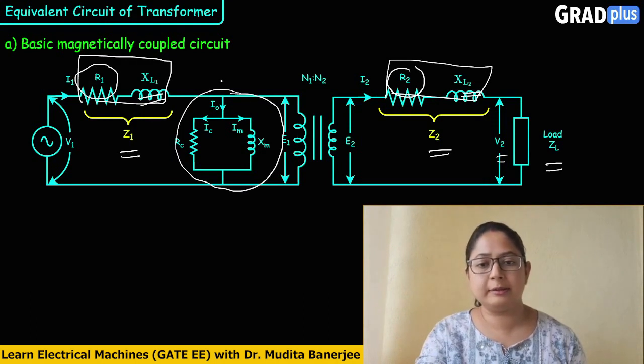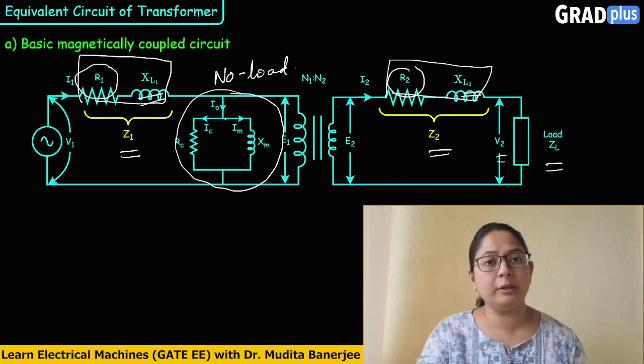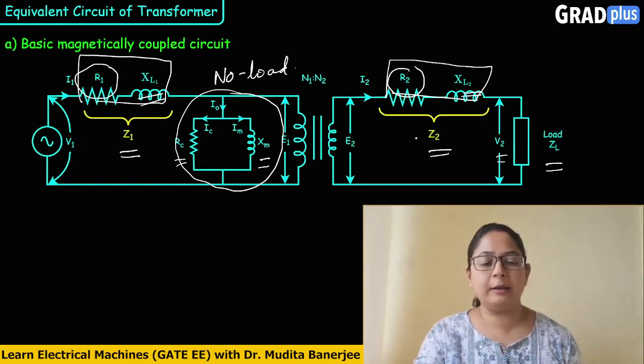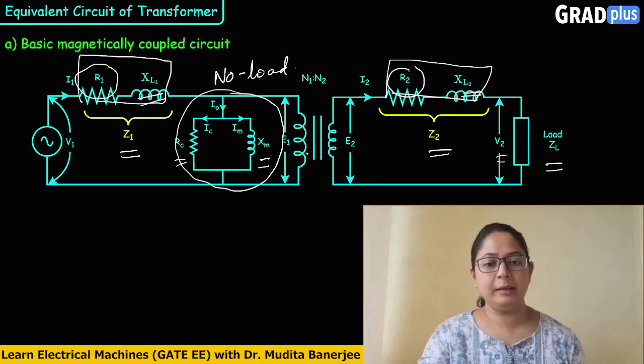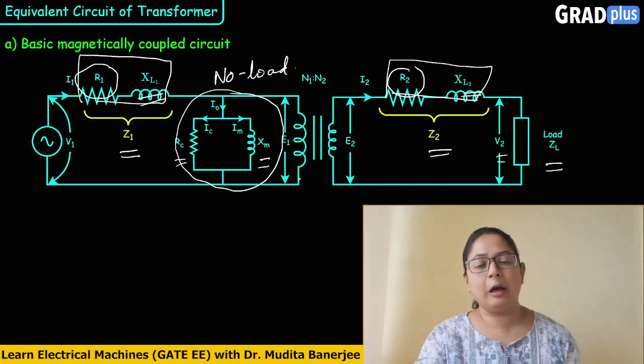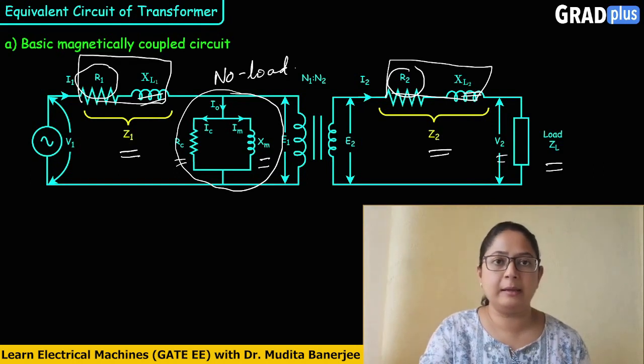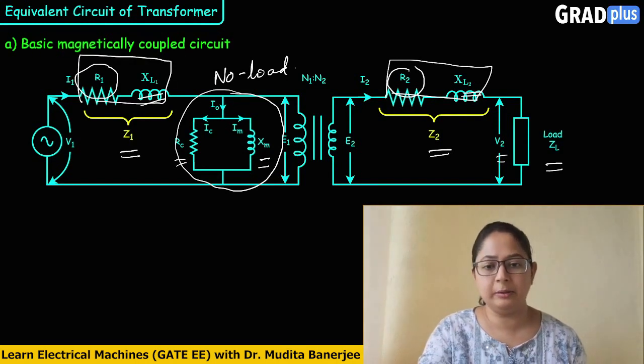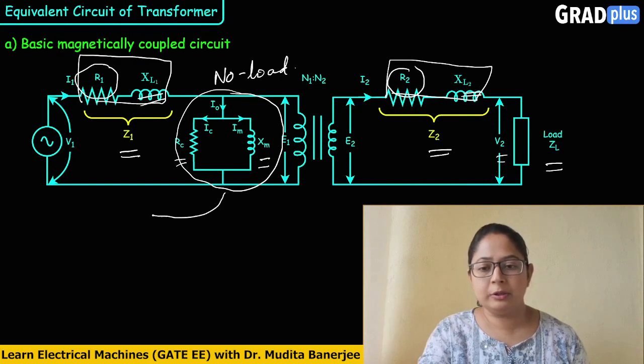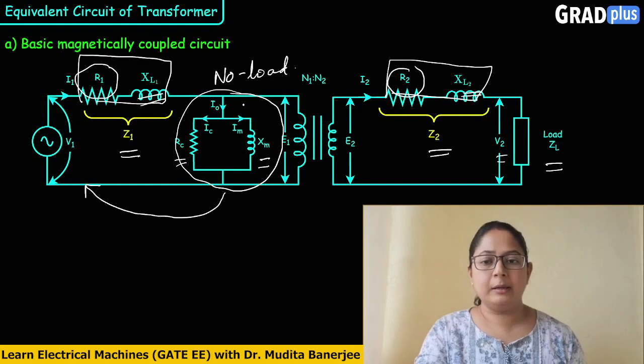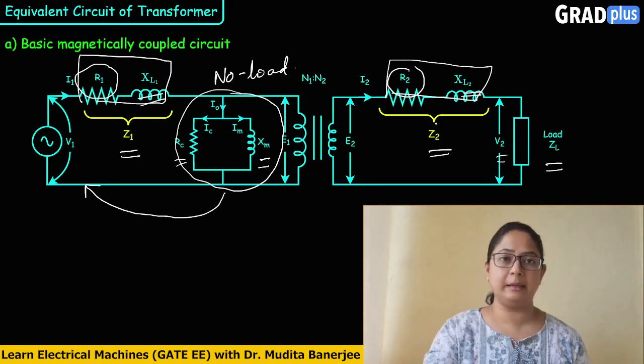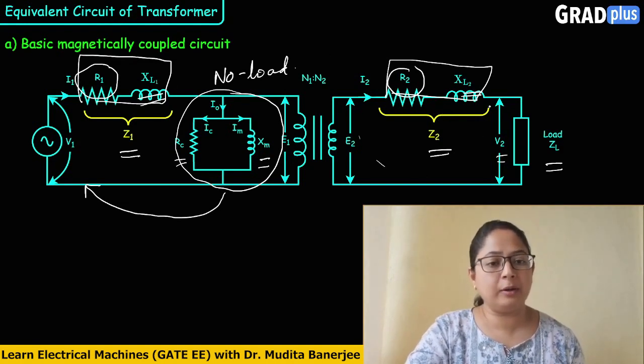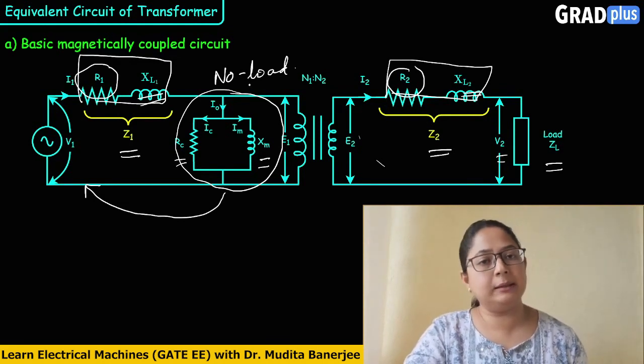There is one branch called the no-load branch, connected in parallel to the supply, in which the no-load current I0 flows. It contains a core loss component and a magnetizing component. E1 and E2 are the EMFs induced in the primary and secondary windings. To make calculations simpler and to calculate efficiency and voltage regulation, the parallel no-load branch is shifted in front of R1, and the entire secondary circuit is transferred to the primary side.